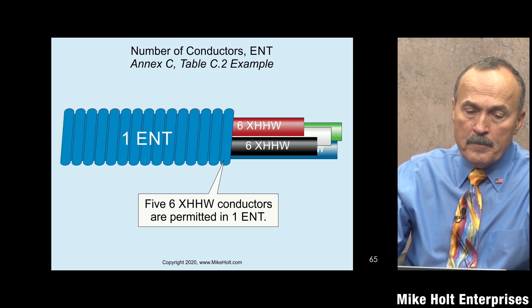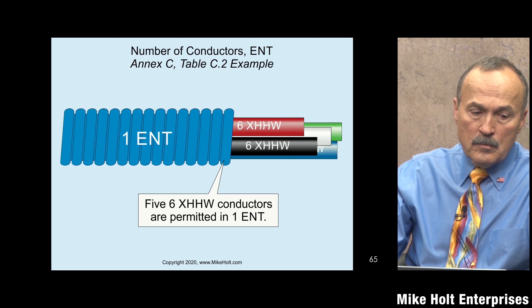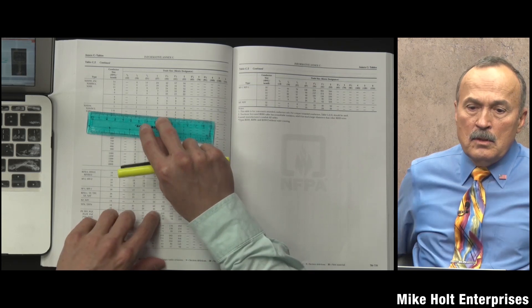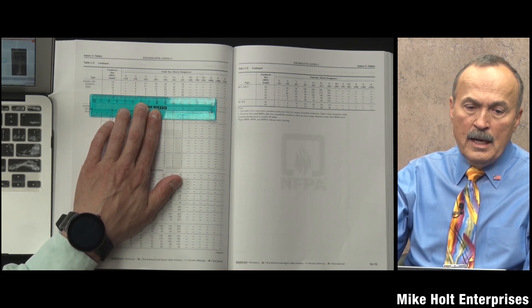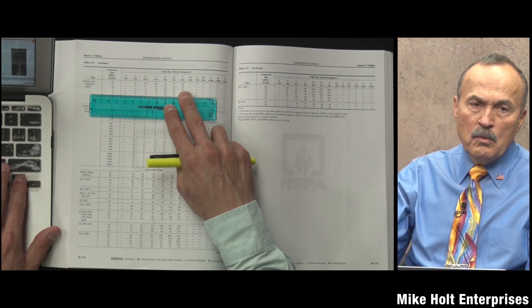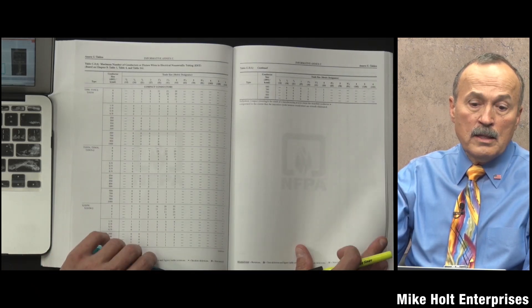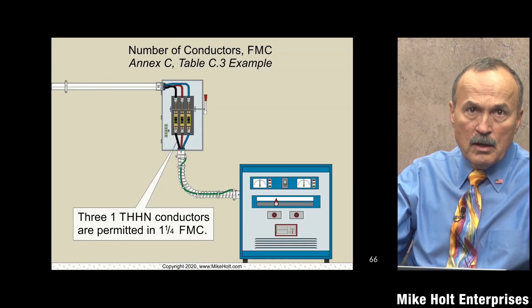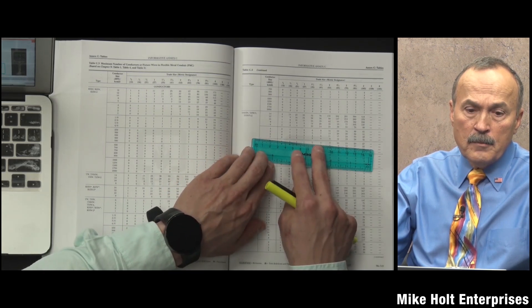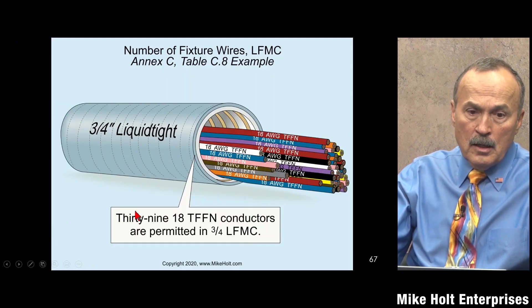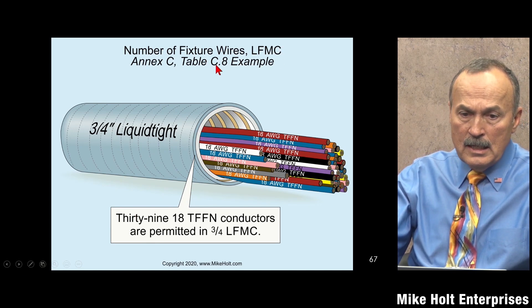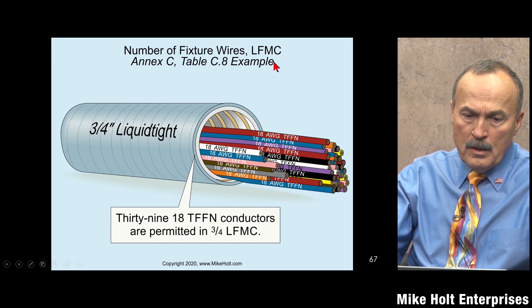Next: five #6 XHHW conductors - can they fit in a 1-inch ENT? For ENT you have to go to the ENT table, look up XHHW, and with five of them a 1-inch ENT is the right size. Then: three #1 gauge THHN conductors - looking at flex metal conduit, going to the 1.25-inch table, three #1 gauge wires fit - so that's correct.